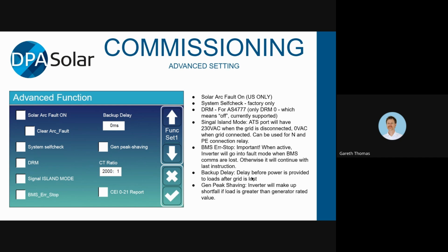Backup delay before power is provided to loads after grid is lost. Not sure why you'd want to do that, but if you want to, that's there. Generator peak shaving, we spoke about that before. If you want to do that, you switch that on. In the example we had, the generator was 8,000 watts. Obviously you've got to have an inverter which is rated for that. But if you were drawing 8,200, it would draw 8,000 from the generator and then draw 200 watts from the batteries.